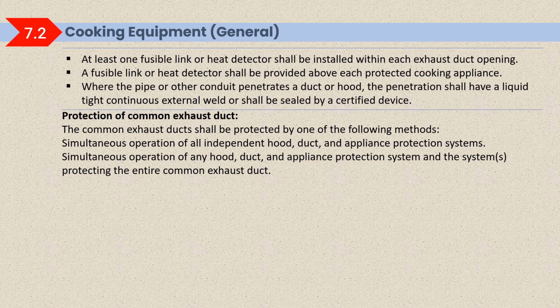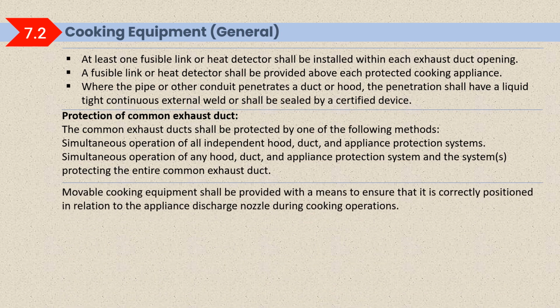The common exhaust duct shall be protected by one of the following methods: simultaneous operation of all independent hood, duct and appliance protection systems, or simultaneous operation of any hood, duct, appliance protection system and the system protecting the entire common exhaust duct. Movable cooking equipment shall be provided with a means to ensure that it is correctly positioned in relation to the appliance discharge nozzle during cooking operation.